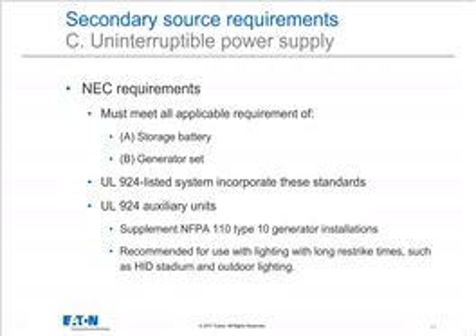the generator starts. So if I'm supporting loads like, for example, high intensity discharge stadium lamps, I know that those lamps, if I interrupt the power even briefly, they're going to go out. And if the power comes back in a half a second, it's still going to take 30 to 45 seconds for those lamps to restrike and turn back on at full brightness, just like the old-fashioned street lights. We know that those are being quickly replaced by high-intensity LED lamps that have longer life and better brightness control and things like that. But for those types of HID lighting, it's a good idea, if I'm depending on the generator for long-term backup, to have a UPS that instantaneously provides support to that lighting so I don't have to deal with a restrike delay. So outdoor lighting like you might find in a parking lot or a parking deck is another example of this type of application.